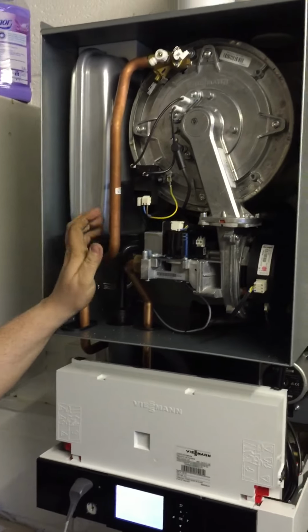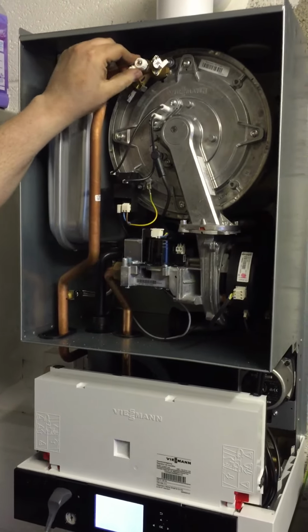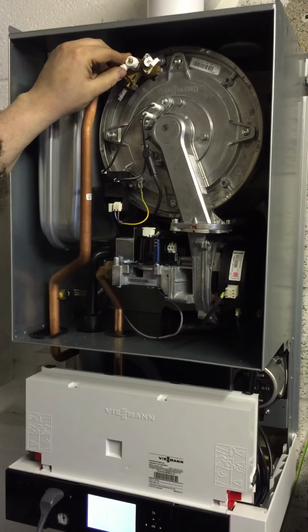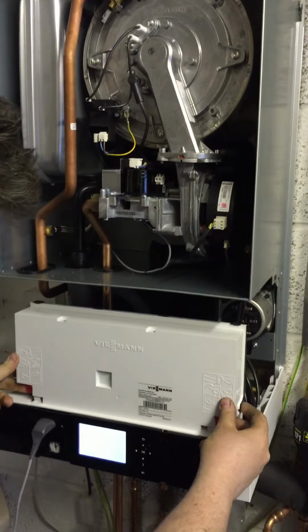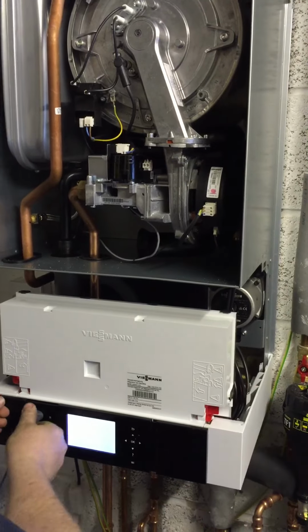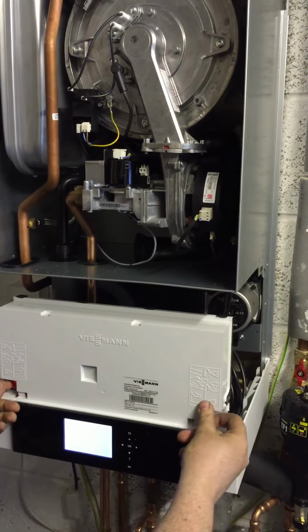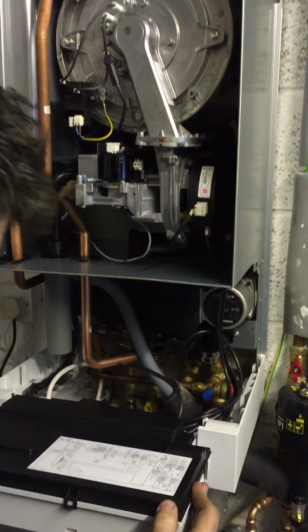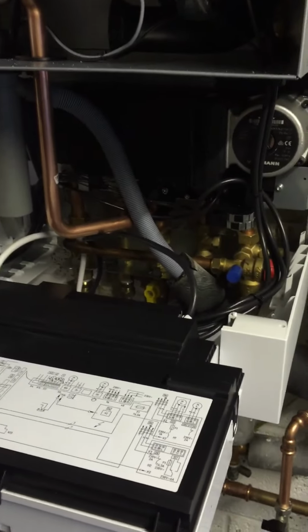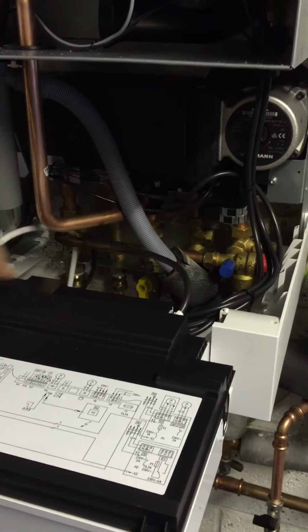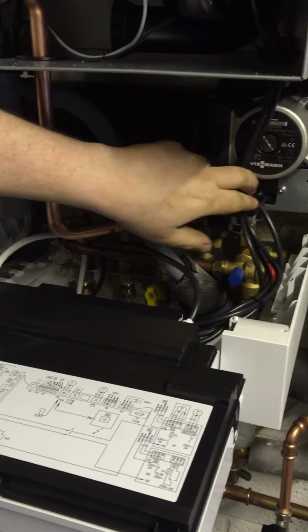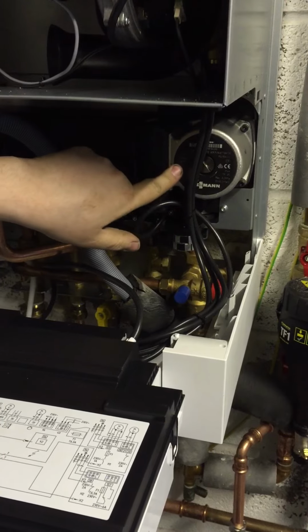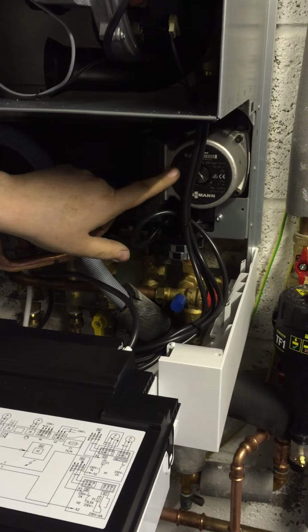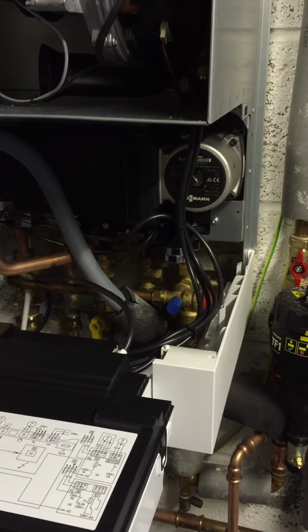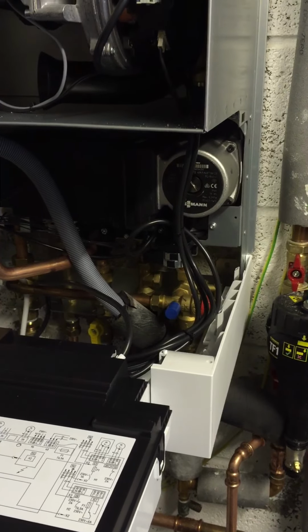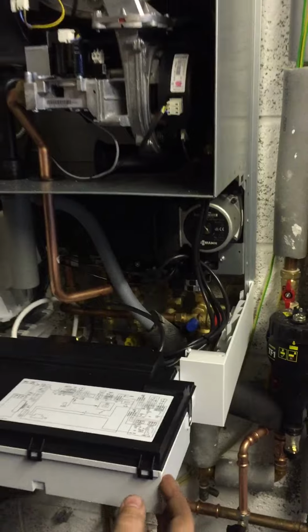Obviously in this boiler we've got more copper and brass than we have in the 100, so we've got the copper return there going back up, bleed point on the top similar to the 100 where we bleed the heat exchanger. If we look at the bottom, we look at the hydro block down here. If you have a look in there, you can see that we've got brass components in the bottom there, brass and copper. We've got a fully modulating pump. This doesn't look like the ErP pumps that we're familiar with in the UK, this Grundfos, but it is fully modulating, and the Viessmann 200's been ErP compliant before ErP was even brought into the UK.